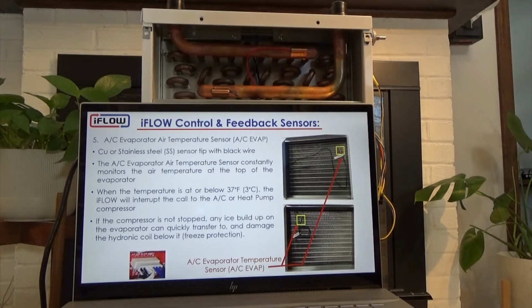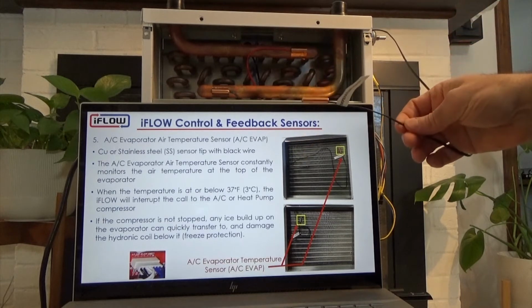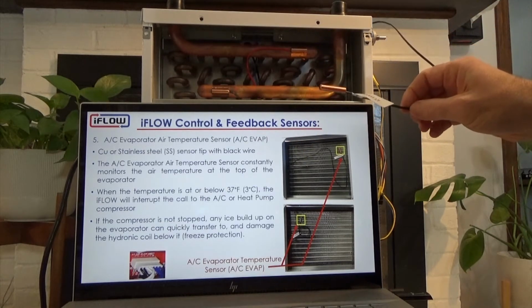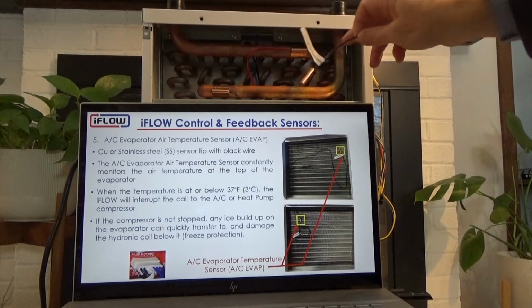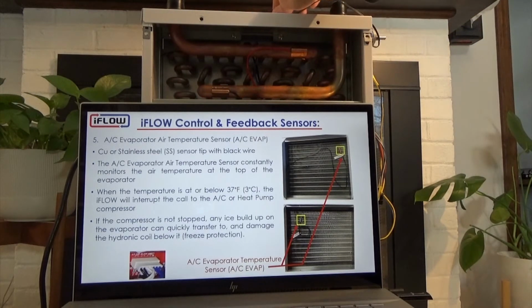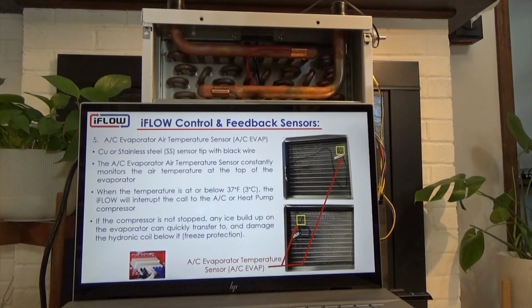So the freeze protection is critical, and that's what this sensor is for. It's providing freeze protection for the AC evaporator, but also, and more importantly perhaps, the hydronic coil that's below the AC evaporator. If you do not relocate that sensor, then you do not have freeze protection, unfortunately.